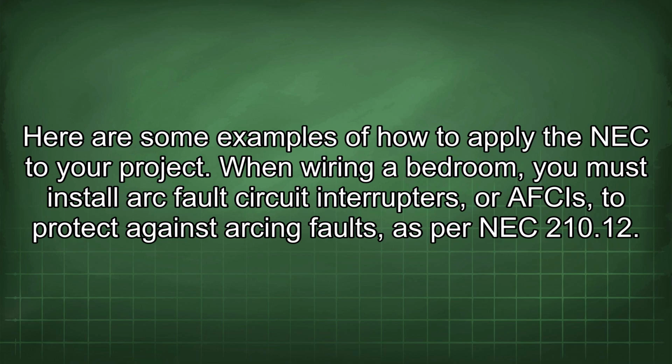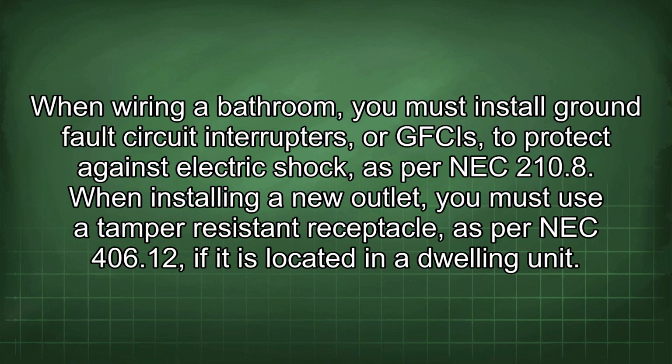Here are some examples of how to apply the NEC to your project. When wiring a bedroom, you must install arc fault circuit interrupters, or AFCIs, to protect against arcing faults, as per NEC 210.12.